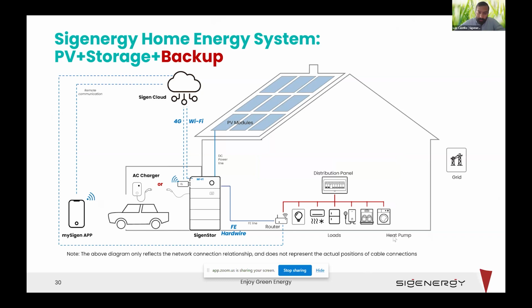Another typical scenario is PV plus storage and backup. Everything remains the same except your AC side. This time you will have a gateway. Your energy controller will be connected to the gateway, your distribution load will be connected to the gateway as well, and the grid in the same way.